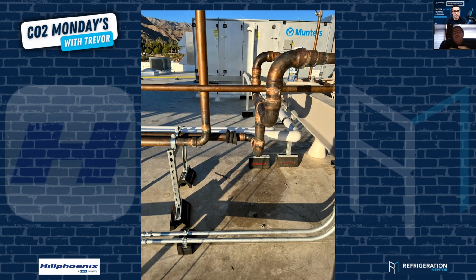So we use Bitzer 85K, BSE 85K. Those switches are calibrated to that Bitzer oil. So if you start using another oil, you're going to start changing the conductance capacity of your oil and changing your switching points, as well as using a non-approved oil.